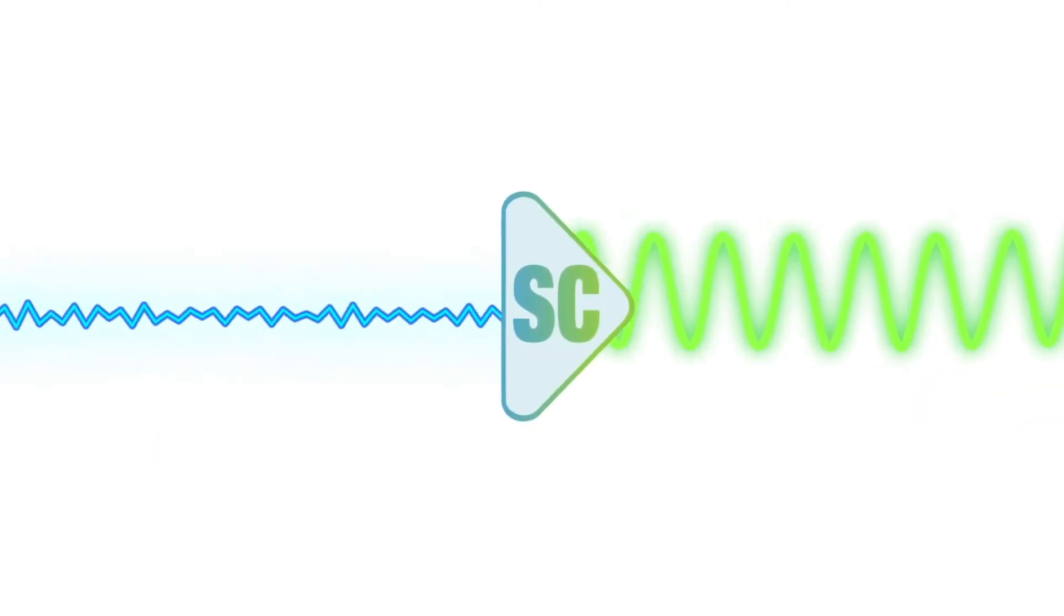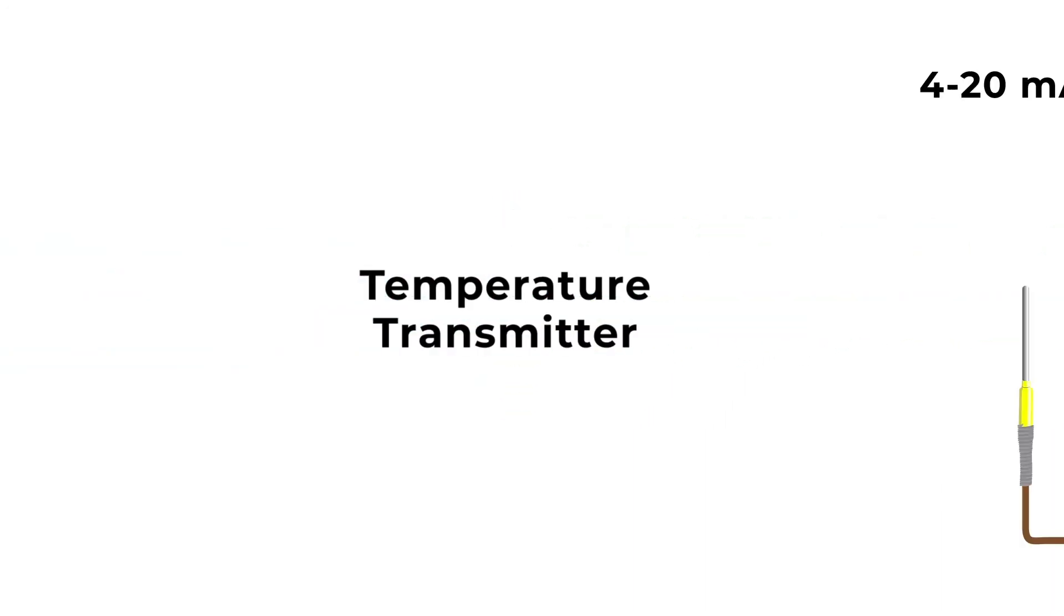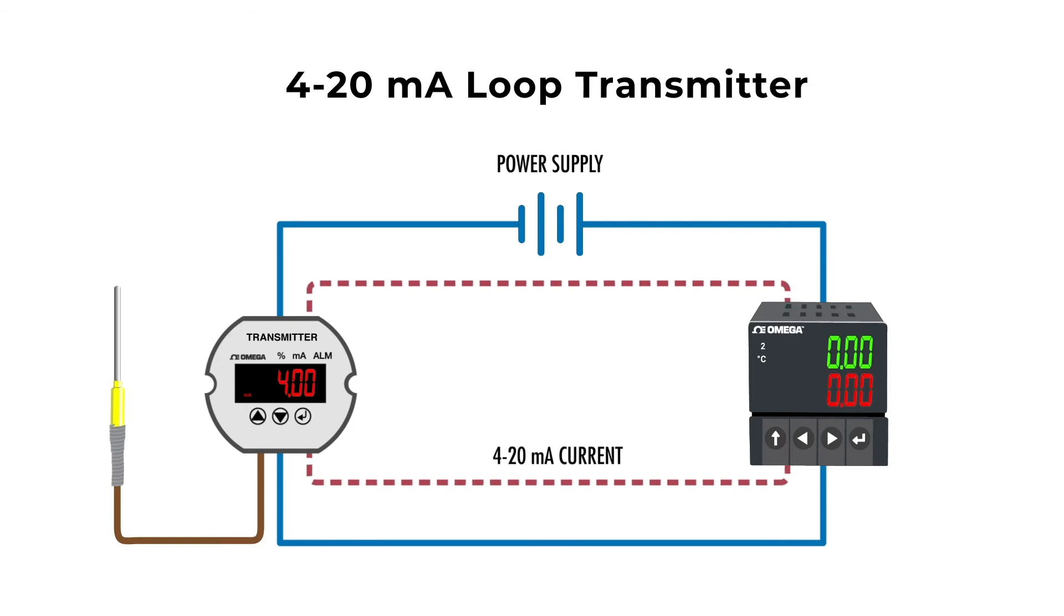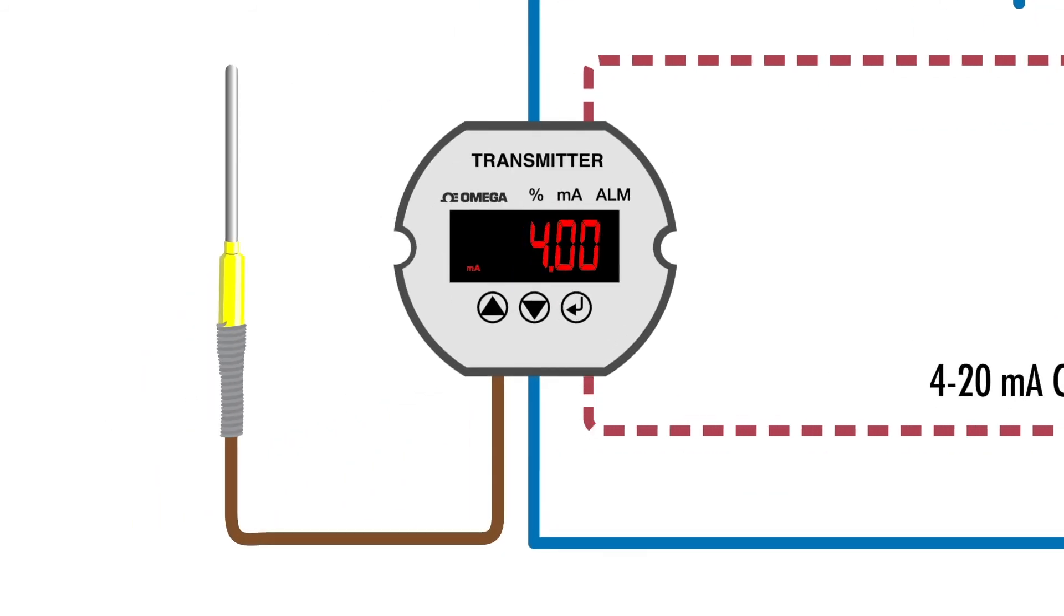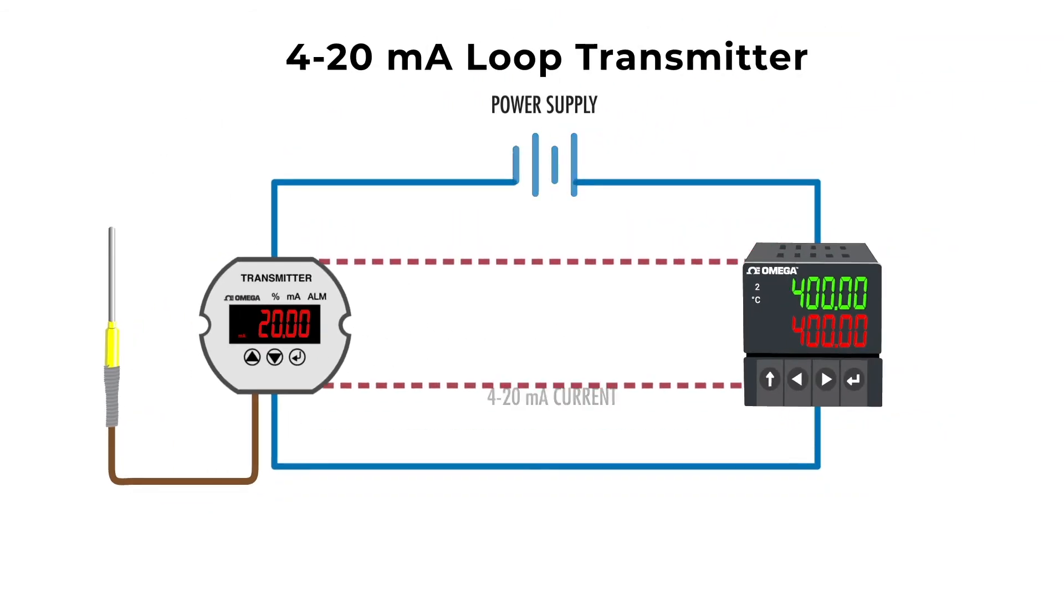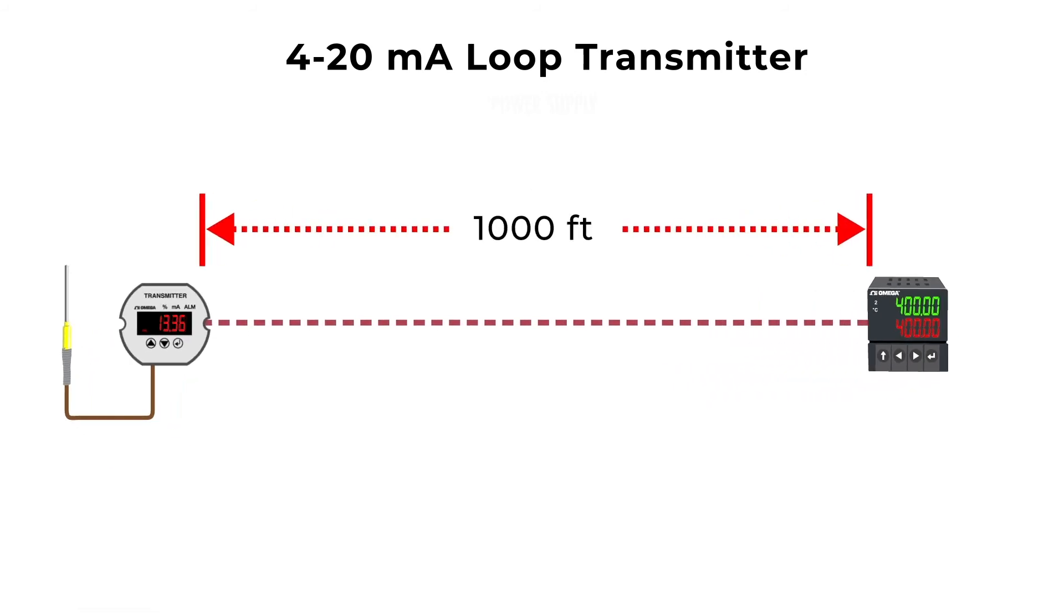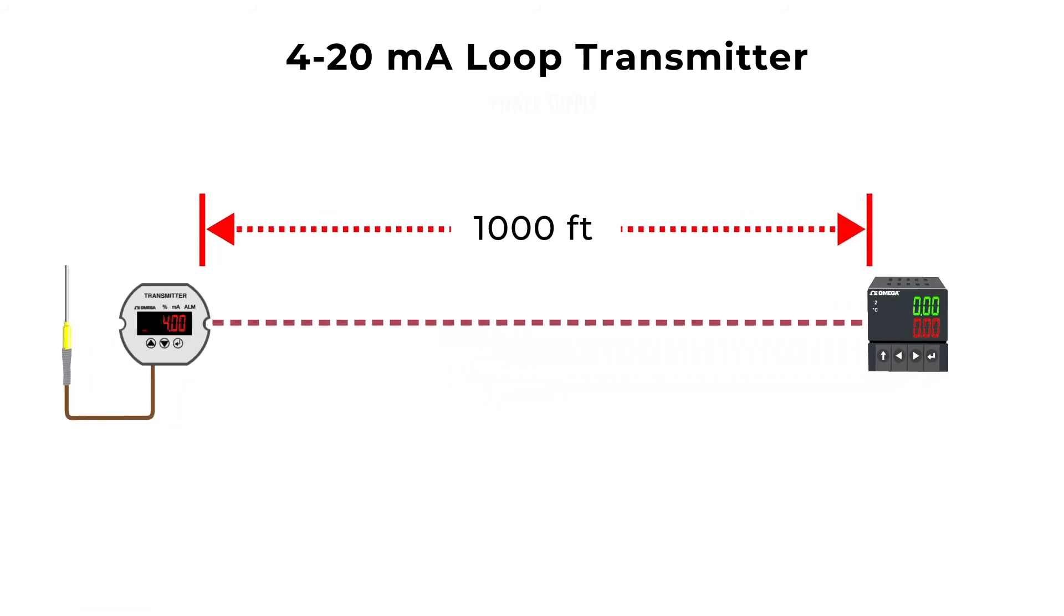Here's where a signal conditioner, like a temperature transmitter, comes into play. A 4 to 20 milliamp loop transmitter is often a low cost and effective solution. The signal is converted to milliamp output, with 4 milliamps representing the low end of the measurement, and 20 milliamps representing the high end. Milliamp current signals can travel up to 1,000 feet without being affected by signal loss due to electrical noise.